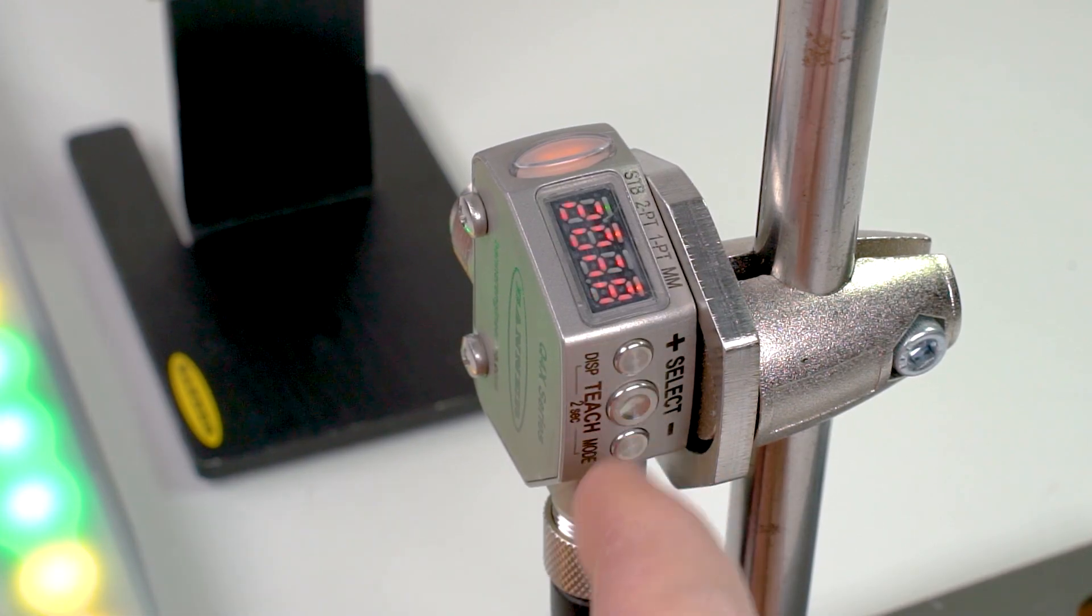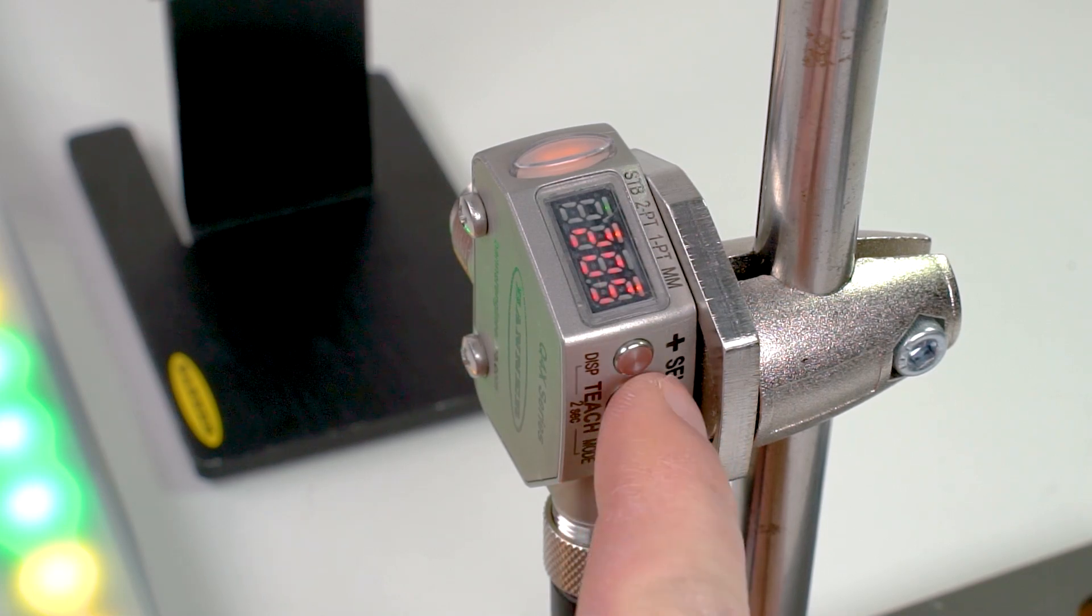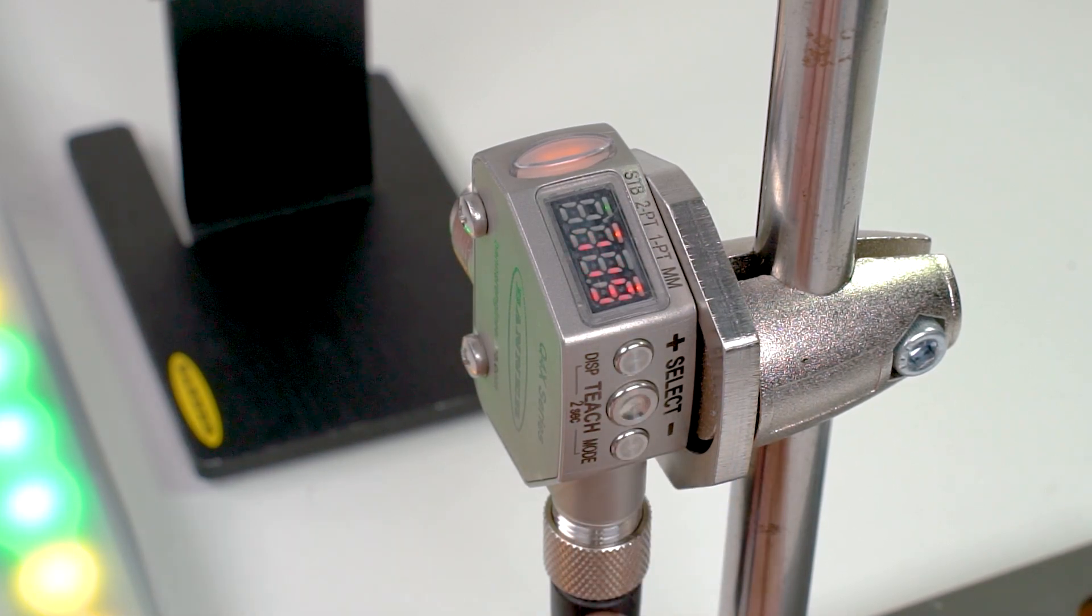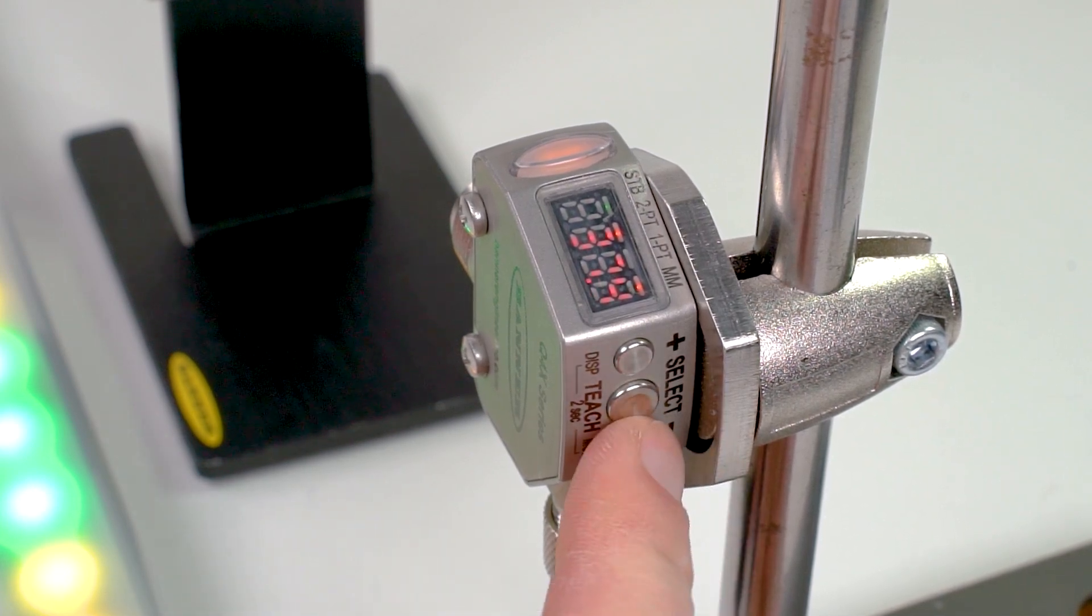Press the plus button to initiate the adjustment for the upper limit of the signal and then use the plus and minus buttons to make the adjustments. Press the select button or leave the sensor alone for two seconds to confirm the selection. Press the minus button to initiate the adjustment of the lower limit and then follow the same process.